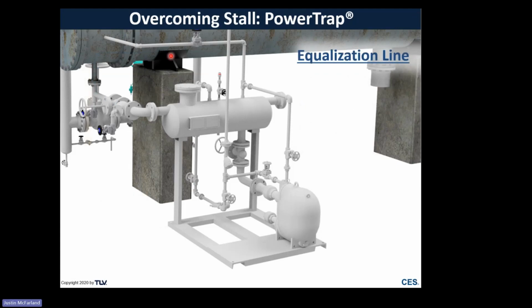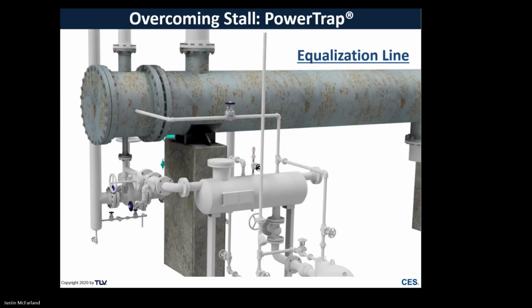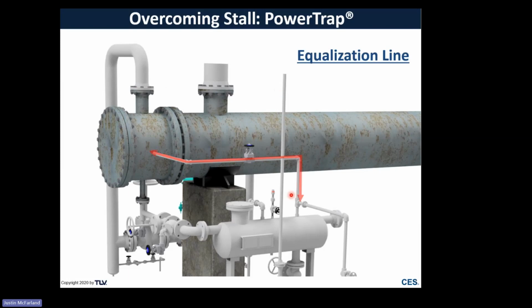So big critical point here is the equalization line, making sure that's properly sized, properly piped from the power trap to the receiver, as well as the equalization line from the receiver to the equipment itself. The whole point is to make sure that the pressure inside the heater is the same as the pressure in our reservoir and is the same as the pressure inside the power trap. If that scenario happens, then condensate can gravity drain down.